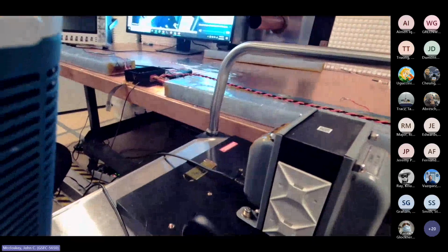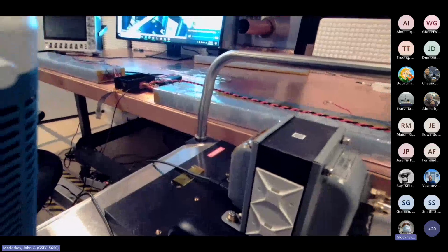Yes. But one way or another, you want to make sure you've got a controlled resistive impedance mapped to the transformer secondary when you're hooked up to an EUT power feed.